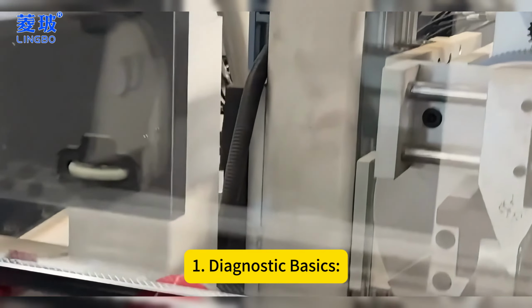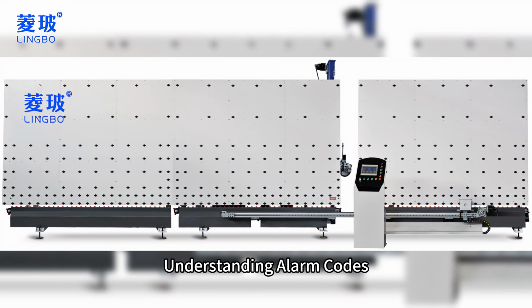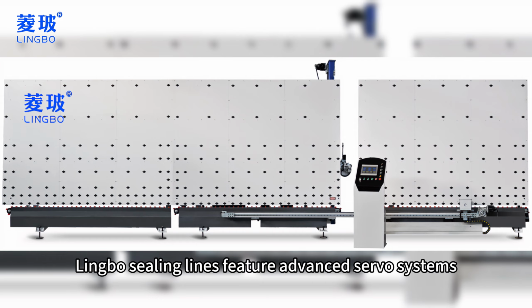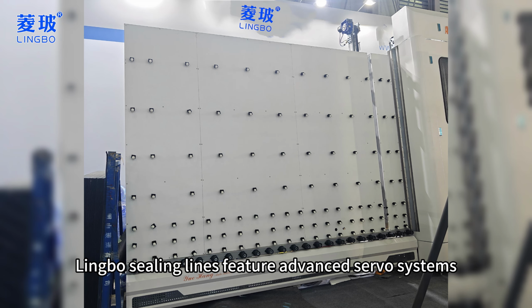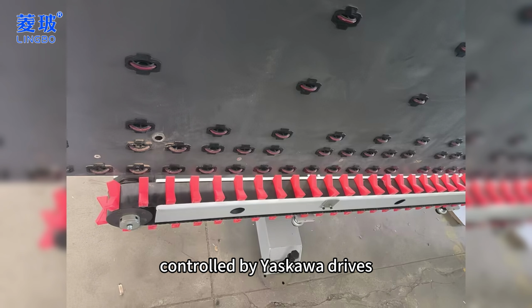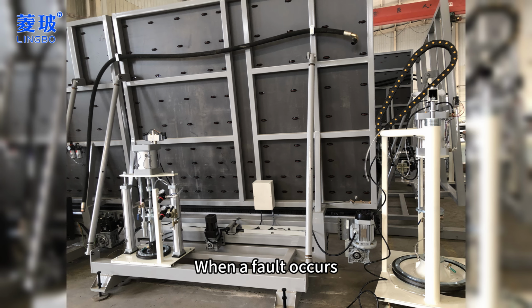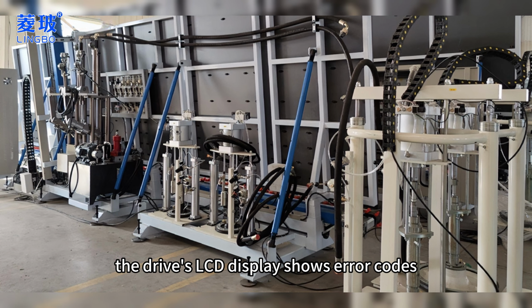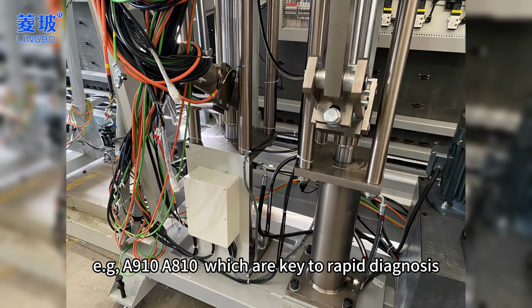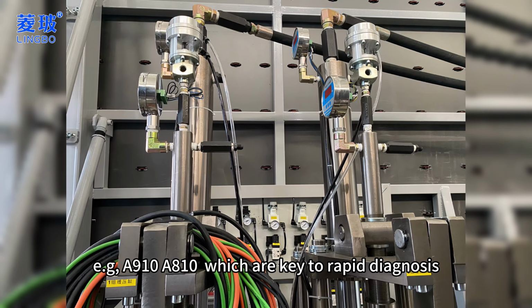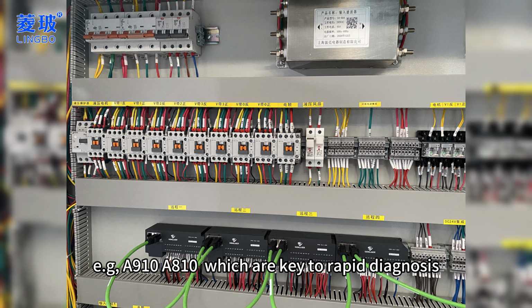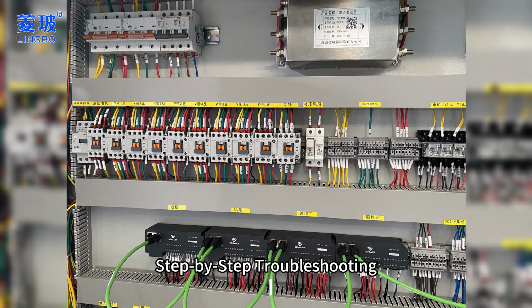Section 1. Diagnostic Basics. Understanding alarm codes. Lingbo sealing lines feature advanced servo systems controlled by Yaskawa drives. When a fault occurs, the drive's LCD display shows error codes, for example, A910, A810, which are key to rapid diagnosis. Step-by-step troubleshooting.